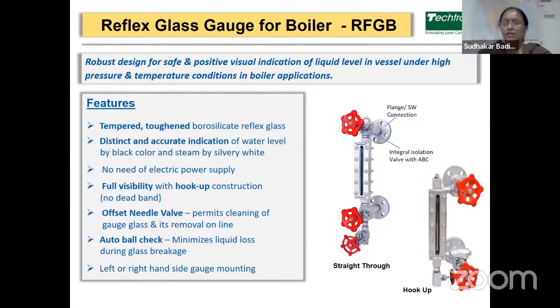as a black color, as the light falls on it, gets refracted into the liquid and it appears as a black color to the viewer, whereas the portion which is covered with air or steam appears as silvery white to the viewer. So clearly you can get the indication of liquid level in a black color. So this is a distinct and accurate indication of water level. Being a mechanical gauge, it doesn't require any electric power supply.